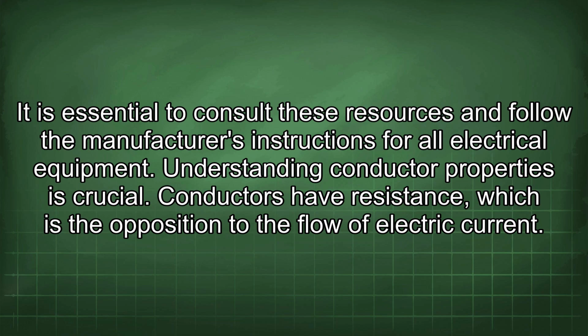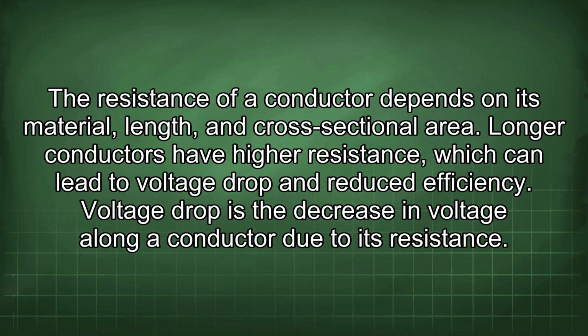Understanding conductor properties is crucial. Conductors have resistance, which is the opposition to the flow of electric current. The resistance of a conductor depends on its material, length, and cross-sectional area. Longer conductors have higher resistance, which can lead to voltage drop and reduced efficiency. Voltage drop is the decrease in voltage along a conductor due to its resistance.